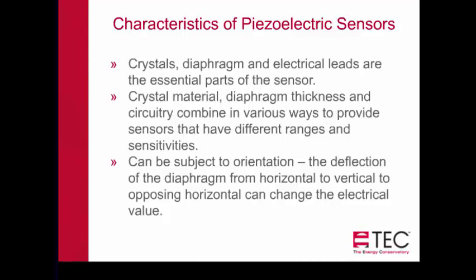Piezoelectric sensors can be subject to orientation. If you have the gauge sitting horizontal on a table, the diaphragm is set to read zero. When you tip the gauge vertically so it's standing on end, the weight of the diaphragm and everything connected with it changes. We need to understand the orientation because it can affect how the pressure sensor responds. Even though the weight change is very small, it can still affect the values we see.